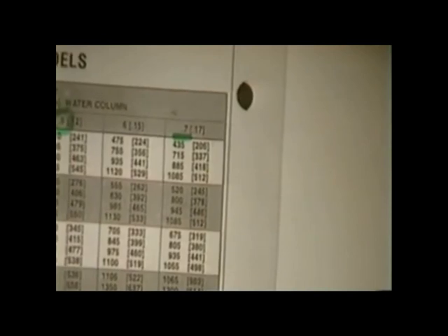Watch. The chart goes beyond the maximum. The furnace is designed for the maximum. It will still work at 0.6. It'll still work at 0.7. But now we start increasing velocity sound and we start losing air. Let's see if that's true.